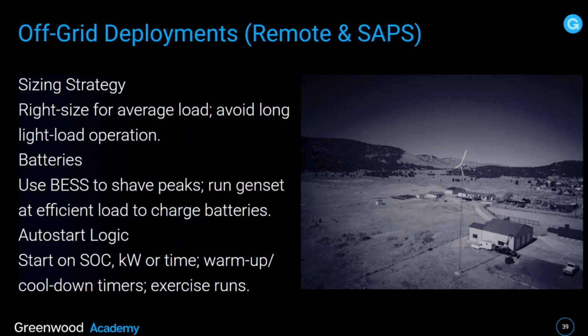So we're going to be looking at sizing strategy, the right size for average load, avoid long light load operations. Batteries, always use them to shave peaks, run the genset at efficient load to charge the batteries. Auto start logic, start on state of charge, kilowatt or time, warm up, cool down, timers, exercise runs. And I mentioned this before, exercise runs are really important, especially when the genset is not called upon frequently to service loads. Think an off-grid situation in summer when there's a lot of solar gain and the genset in a lot of cases is not needed.